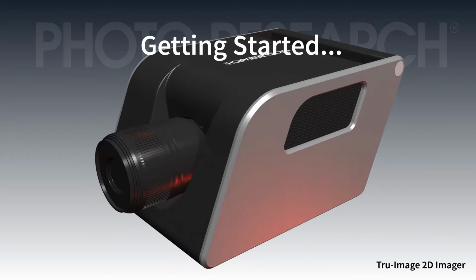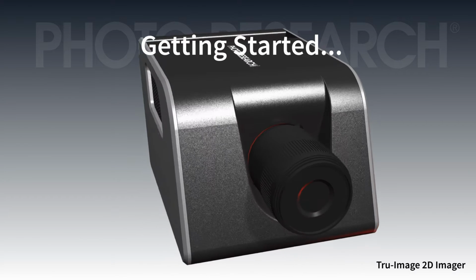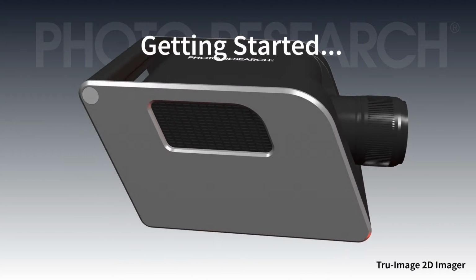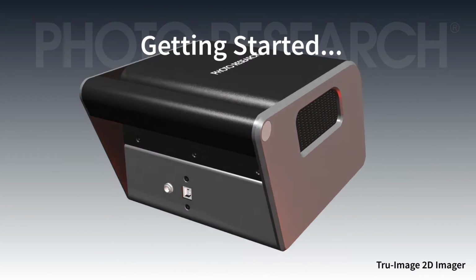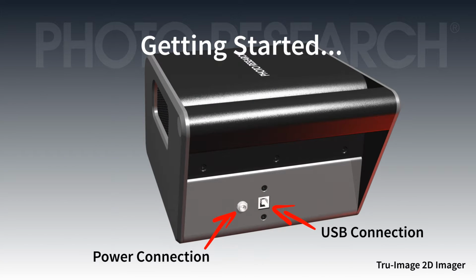Displays and instruments need to be warmed up before any serious measurements or calibrations can be performed. So, power up the Tru-Image, connect it to the PC, and load the matrix calibration software. Make sure the display to be calibrated is turned on and at full brightness. A half-hour warm-up should be enough.